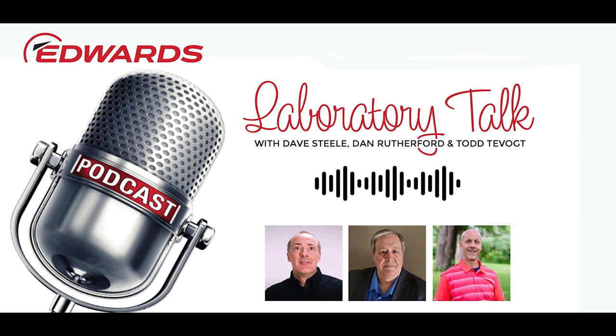One major thing we've improved with these two gauges, the AIM 200 and the WRG 200, is we've dramatically been able to reduce the magnetic stray field. For those who aren't in the loop, magnetic stray field is a real pain. Stray field is the magnetic field which is emitted from the gauge. So if you're fitting these gauges into an environment where there is potentially sensitive equipment in the vicinity, very nearby, it can cause some problems.